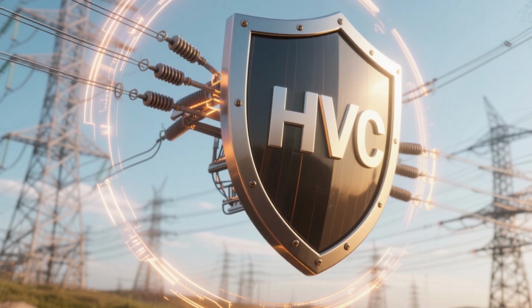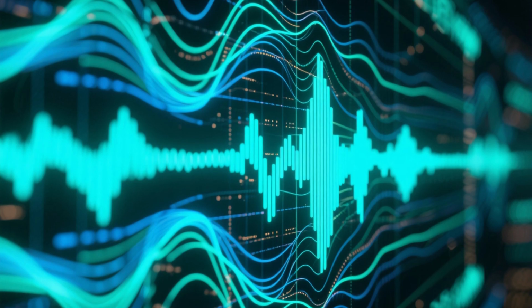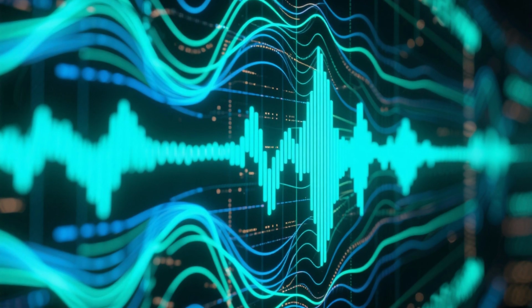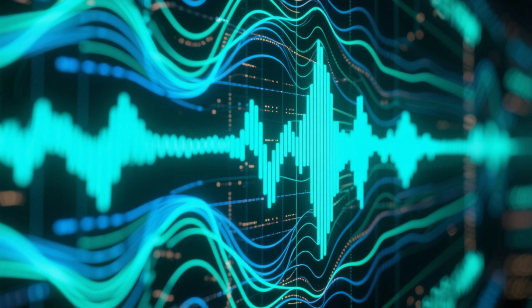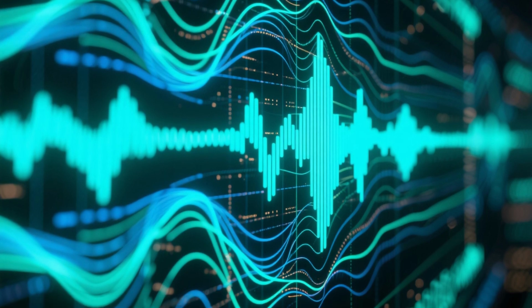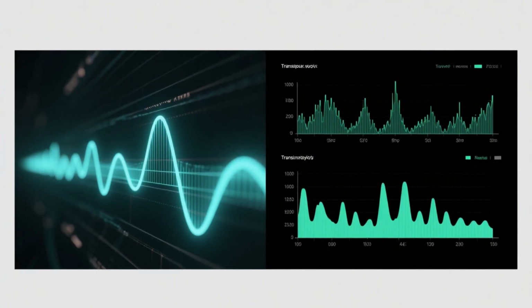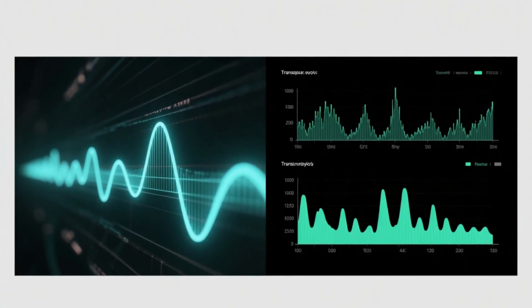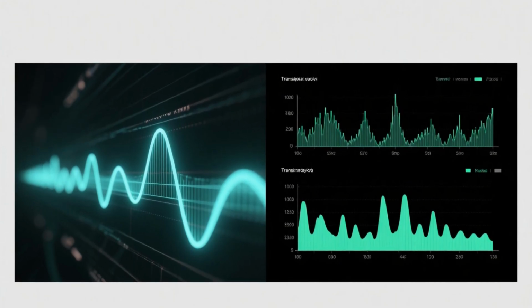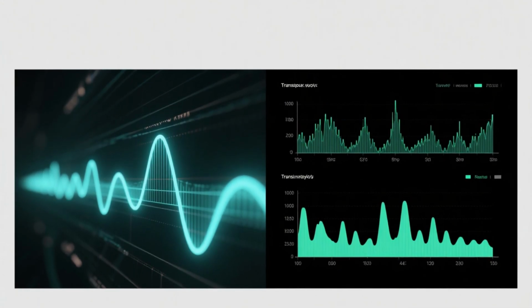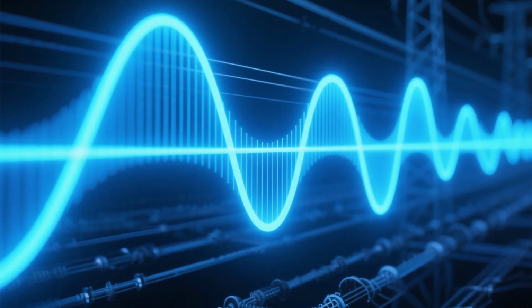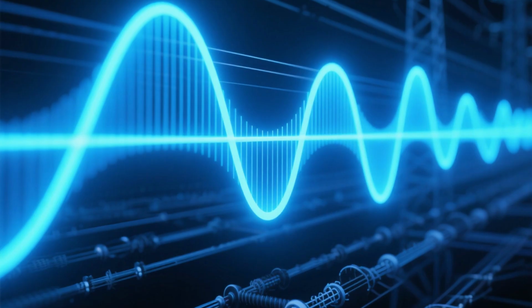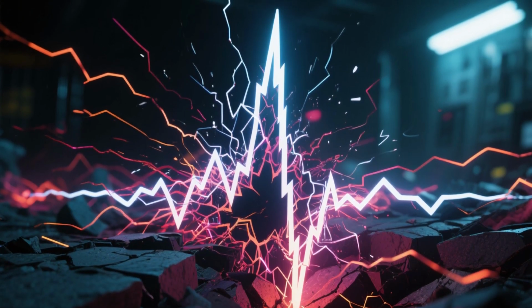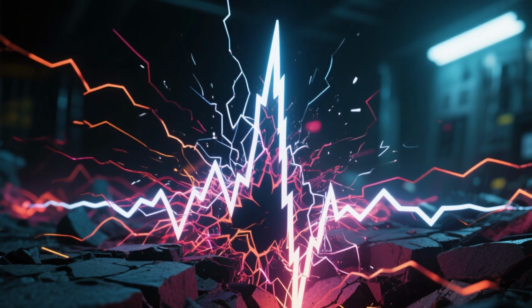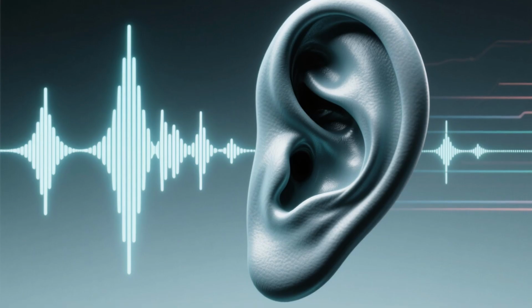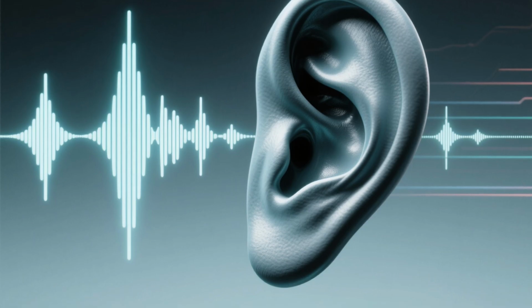Building on the concept of analyzing sudden changes, another powerful primary protection strategy involves transient analysis using advanced signal processing techniques. While traveling wave methods focus on the initial wavefront, transient analysis takes a broader look at the high-frequency disturbances that a fault introduces into the system's voltage and current signals. Think of the normal, steady-state operation of an HVDC line as a pure musical note. A fault is like a sudden, jarring noise that disrupts this harmony, introducing a cacophony of different frequencies. The job of transient analysis is to listen for and identify this noise.